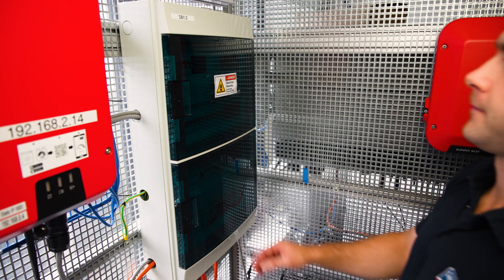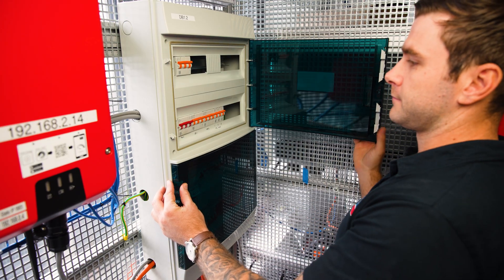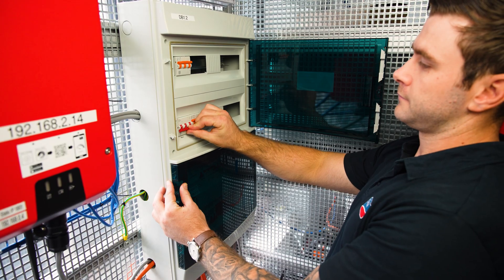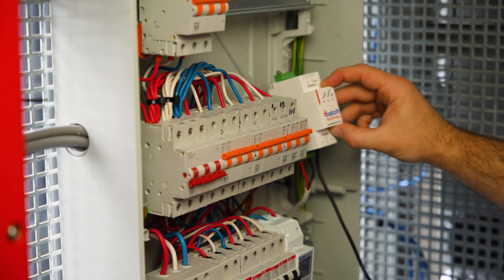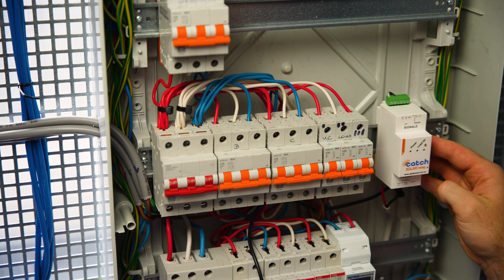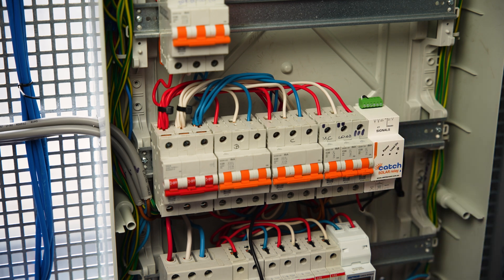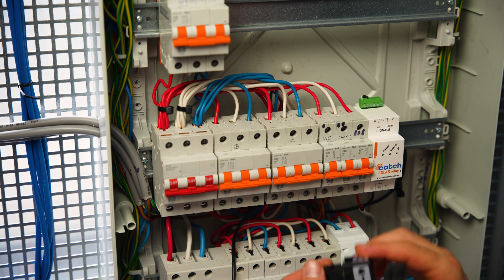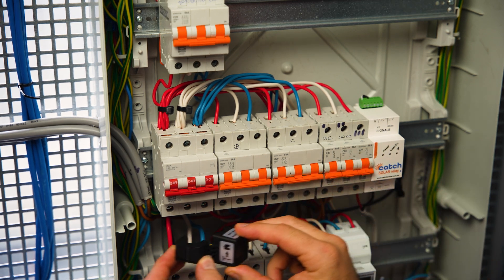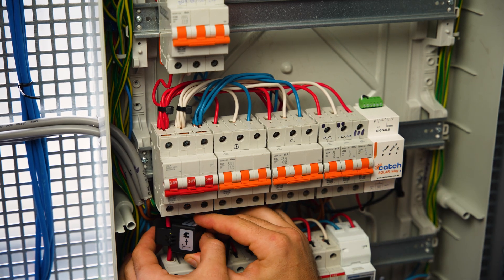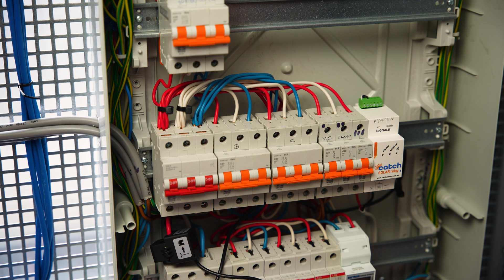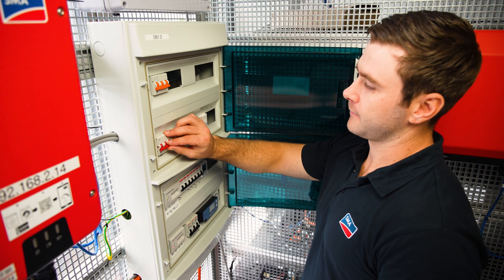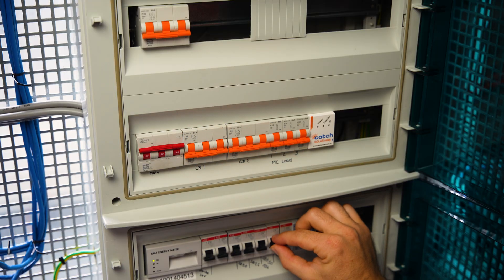It's time for installation into the switchboard. First we make this safe by turning off the main switch. We connect the AC side of our Catch Control into a 10 amp circuit breaker and mount our Catch Control unit onto the DIN rail. We run the CT cabling through the board and connect to the main supply, ensuring the directional flow of the CT is correct from grid to load. We now turn back on our main switch and Catch Control circuit breaker.